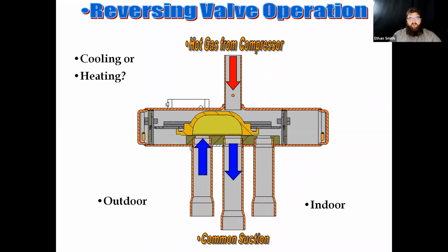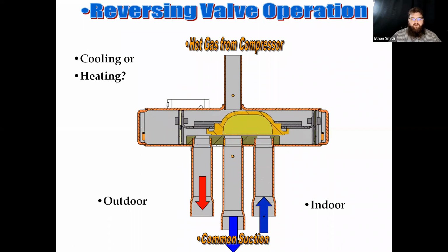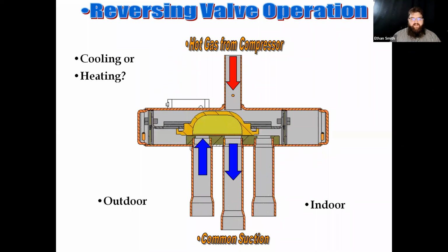Yep, this is in heating mode because we are sending hot gas from the compressor to the indoor coil. Now, we want to switch modes. We fire up that pilot valve. We move the pilot valve over, and the whole rig switches. This is usually accompanied by a loud whooshing noise, also referred to as the whoosh bang.